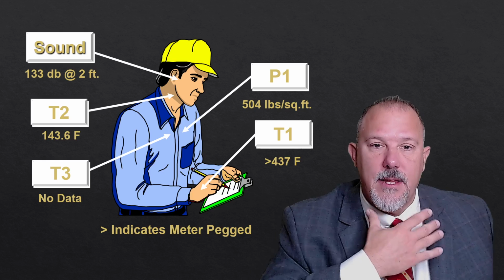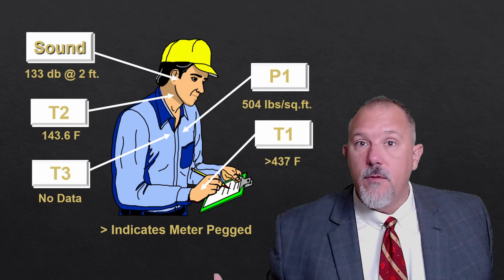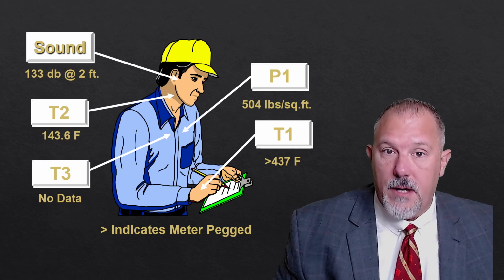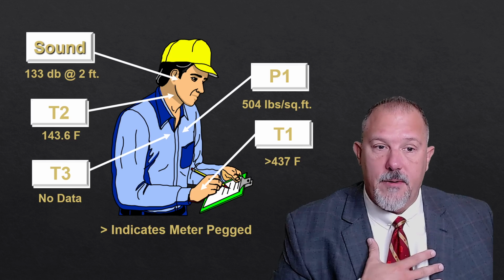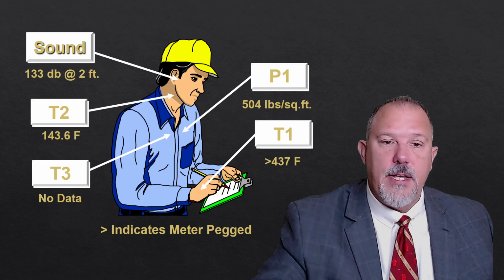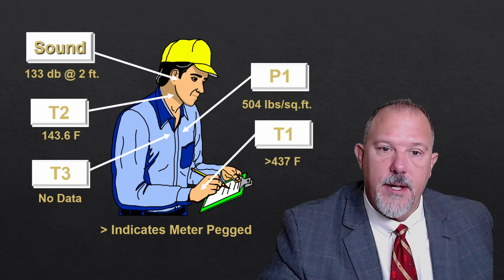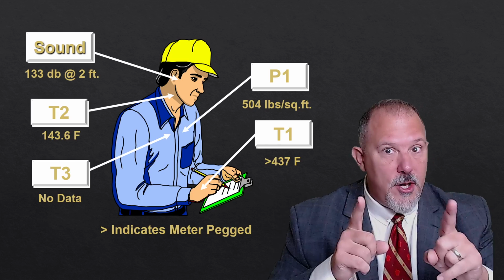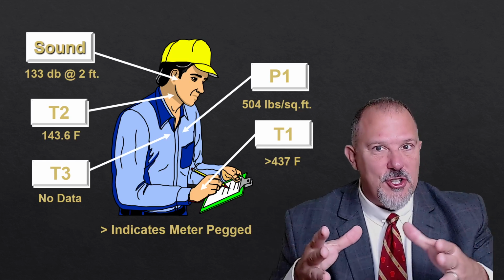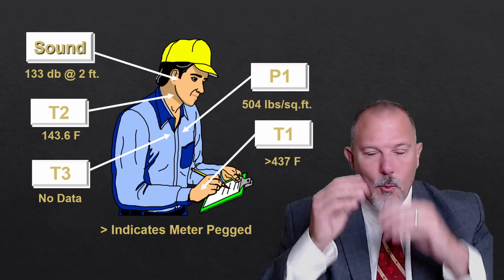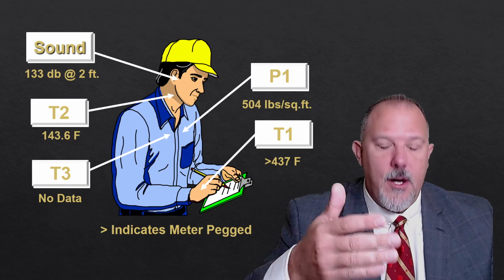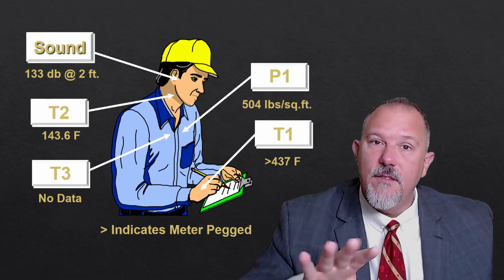143.6 degrees Fahrenheit at the neck, 504 pounds. We went from over 2,000 pounds to 504 pounds per square foot on the chest area, and we didn't have any measured heat on the chest area. So what do we do? What do we know? We know the arc flash boundary is much smaller now. Because remember, what is an arc flash boundary? We knew the first event was around 4 calories.